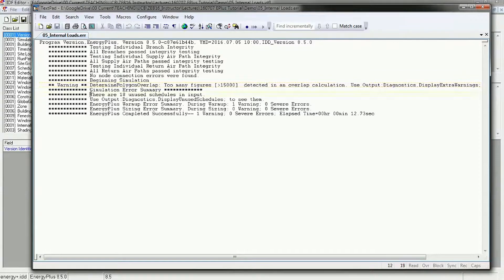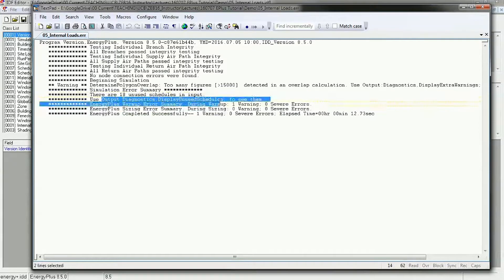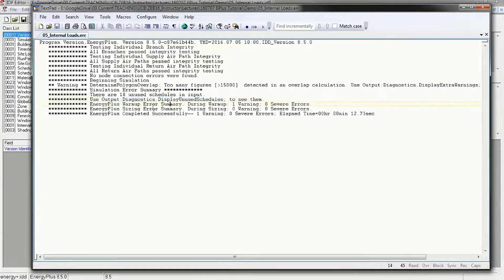It also says there are 18 unused schedules in the input — that's fine, it just means all those extra schedules for schools, offices, residential, and hotel are not being used. You can also use output diagnostics display unused schedules to see them. You'll probably also get a warning that says your weather data was taken at a place it didn't expect, and that's going to be fine because when running different weather files the program won't know exactly where it is until you run the climate file — it still works just fine.